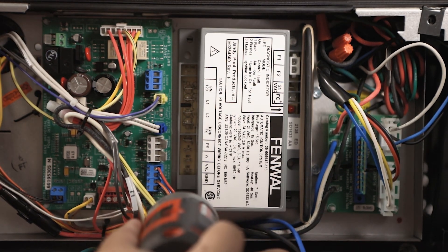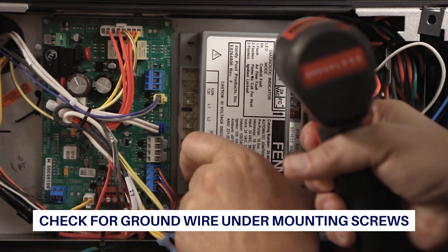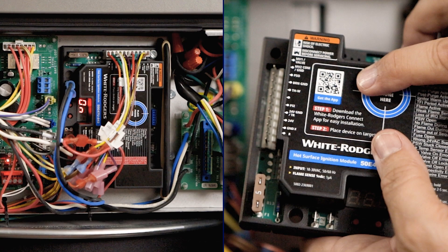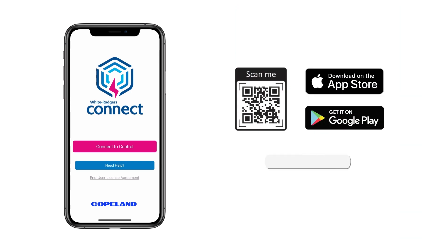Once all wires have been disconnected, remove the existing module. Take note if there is a ground wire attached to one of the mounting screws. For this application, no ground wire is attached. The module can be configured by two different methods. On-board configuration can be done after the module has been installed and powered up. Mobile app configuration is the preferred method and can be done prior to installing the module. Use the QR code on the product label to download the app, or search for White-Rodgers Connect in your mobile device's app store.